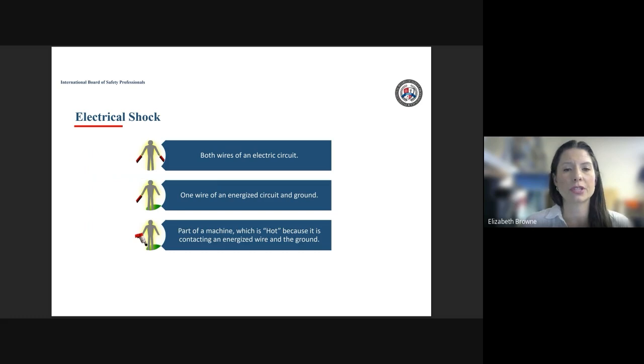So the first hazard we talked about was electrical shock. That occurs when both wires of an electrical circuit, if a person is touching those, as we see in this picture here, so both the positive and negative wire. We generally see those wires in colors of black as positive, or black is neutral or negative, and red as the positive or hot wire. But I have definitely seen situations where that was not the case. So we always want to, if we're a qualified electrical worker, test all wires to ensure that we understand what we're dealing with and not just assume that black is neutral or the ground and red is the hot wire.